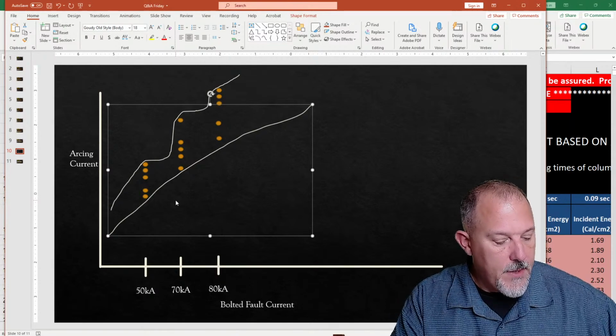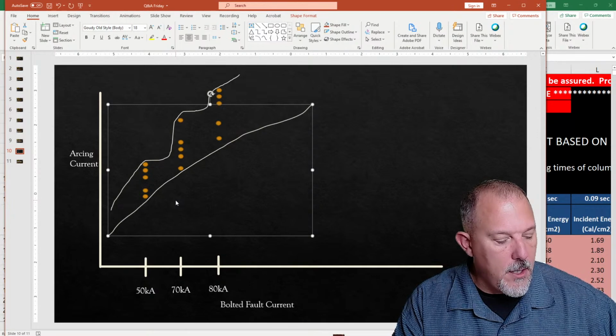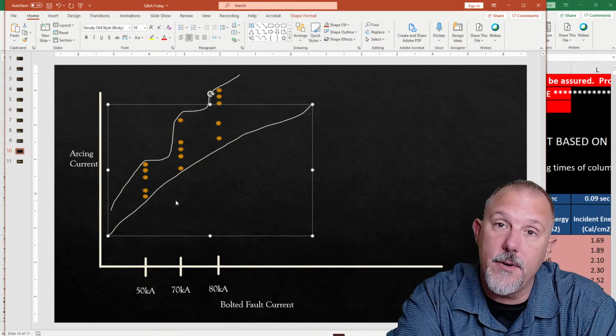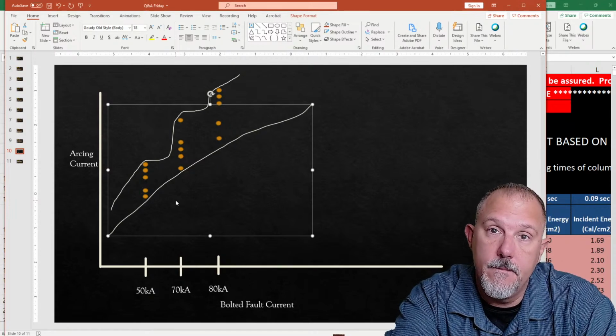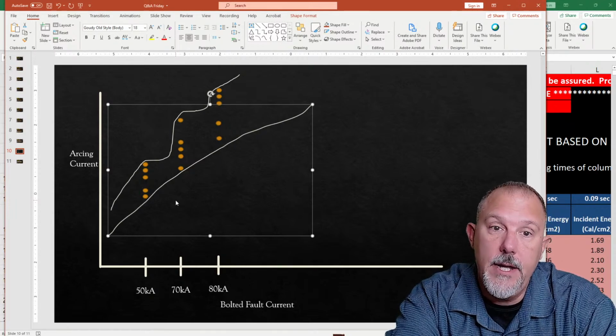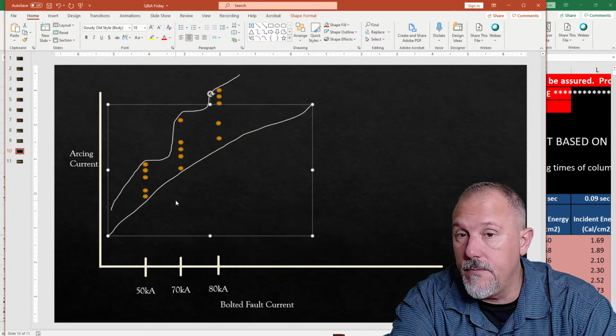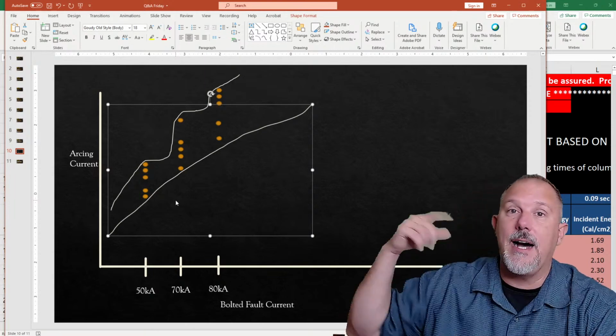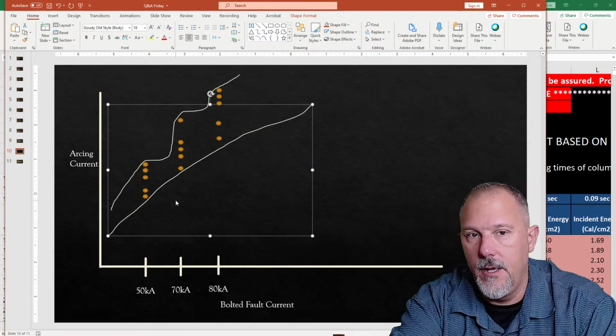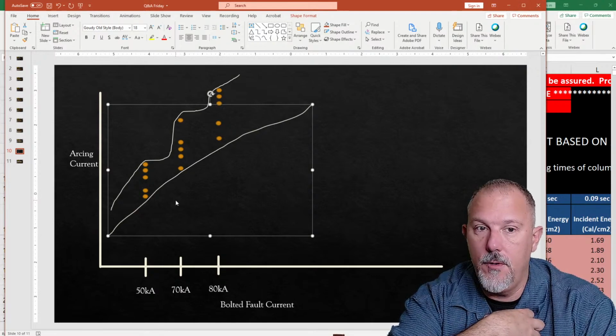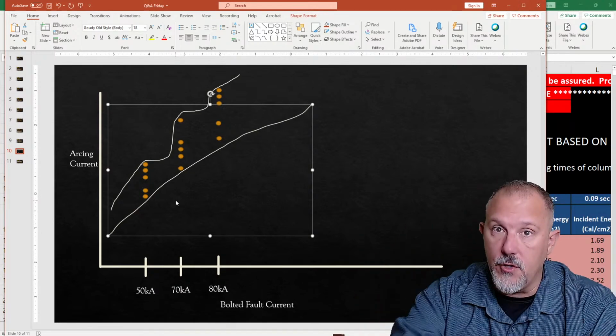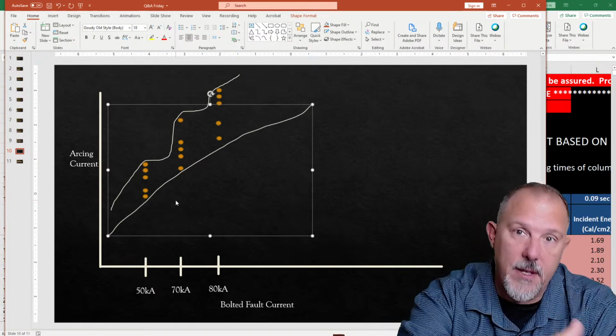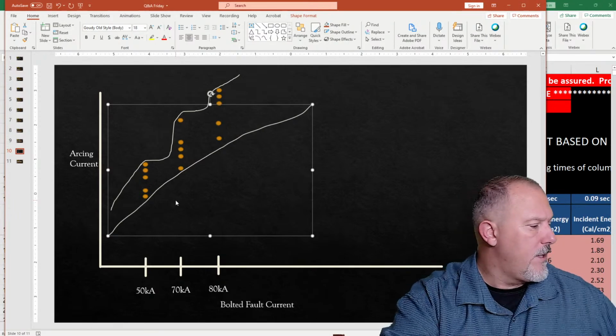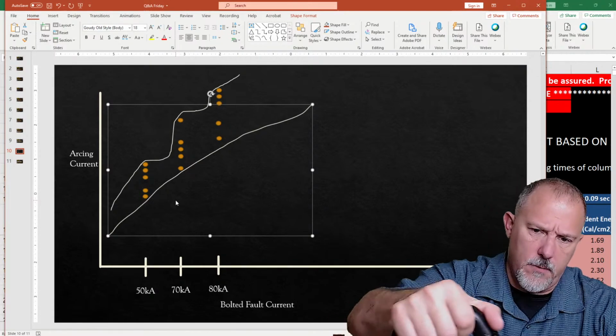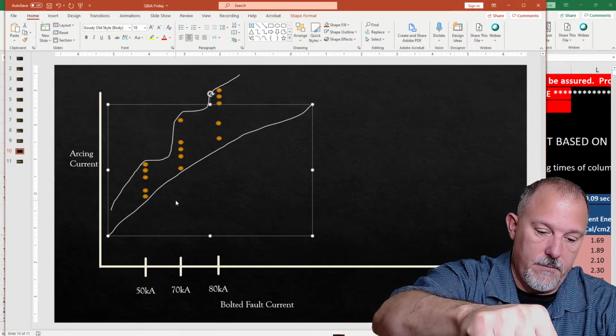24087 says that the clearing time is set to operate at the value below the available arcing current. But which arcing current? We don't say. We just say arcing current. And I could not say you are wrong if you use the higher of the two arcing currents. But as an engineer, I know I would have to use the lower of the two arcing currents, because that will give me a longer clearing time. Capiche?